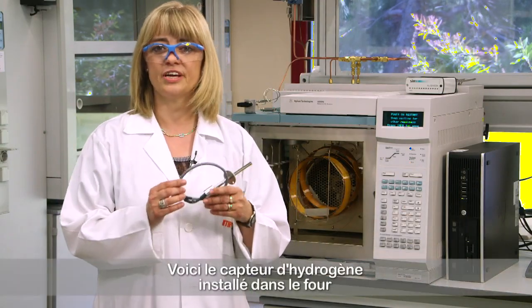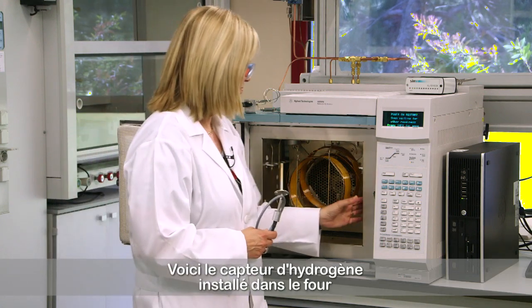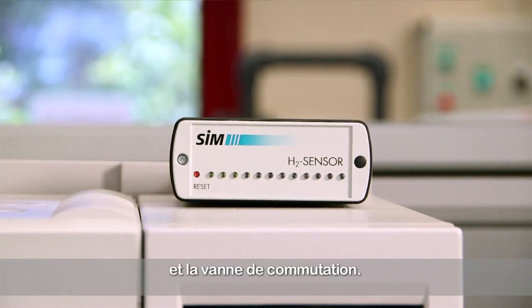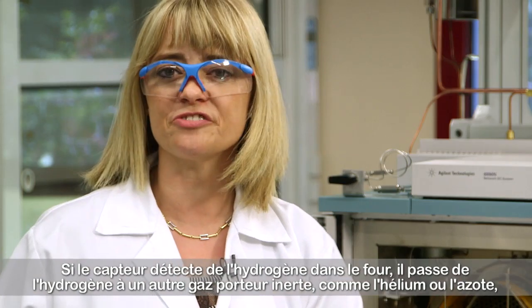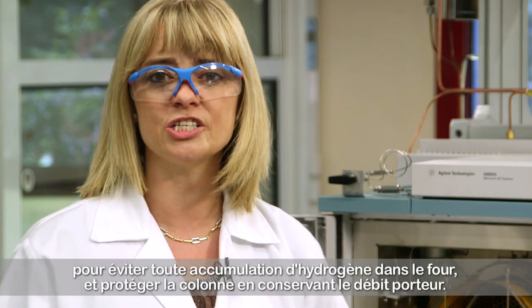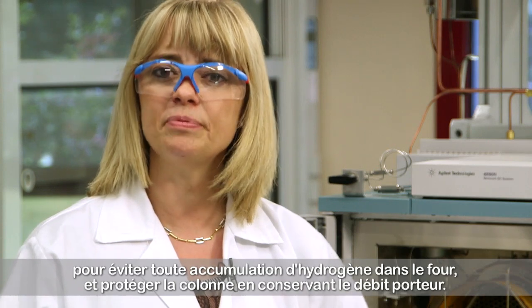Here we have the hydrogen sensor installed inside the oven and the switching valve. If the sensor detects hydrogen in the oven, it switches from hydrogen to another inert carrier — like helium or nitrogen — avoiding the hydrogen accumulation in the oven and protecting the column by keeping the carrier flow.